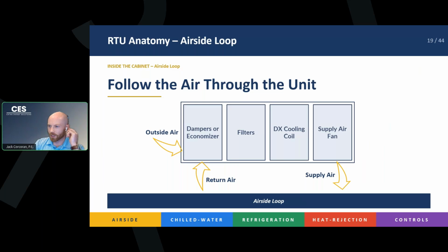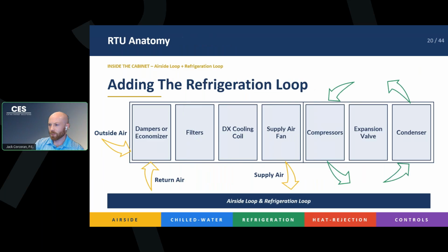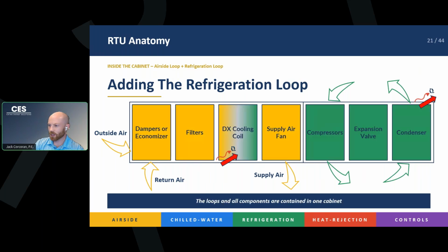Right, so we just followed the air through the unit. We followed it through these four portions, and we talked about a heating coil section and the reheat section. But we can also add in our refrigeration loop. If we want to see where it actually overlaps, we can look at this color diagram. Our green components are part of our refrigeration loop, and our yellow colored sections are our airside loop. So our DX coil is where it all meets. We talked about that a little bit earlier. That's where we absorb the heat from the airside loop into the refrigeration loop, which is our little Q squiggly arrow here. And then it gets rejected into the atmosphere at our condenser, which is where the other Q squiggly arrow is.